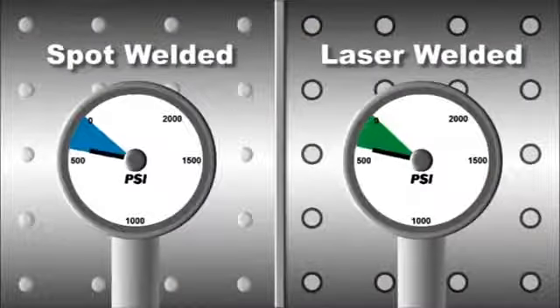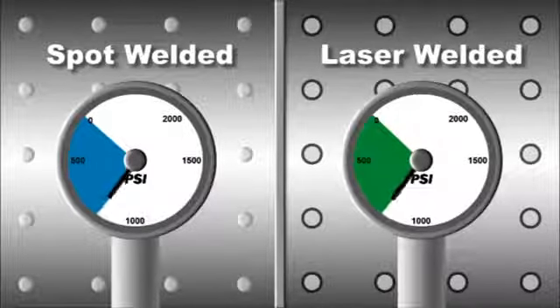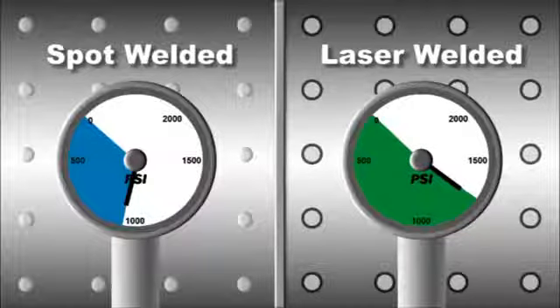The fully welded dot on the KoolWay laser welded panel is stronger than spot or resistance welding used on competitive panels. In ASME testing, the laser weld withstood a burst test of 1,300 psi versus only 970 psi for a competitive resistance weld.